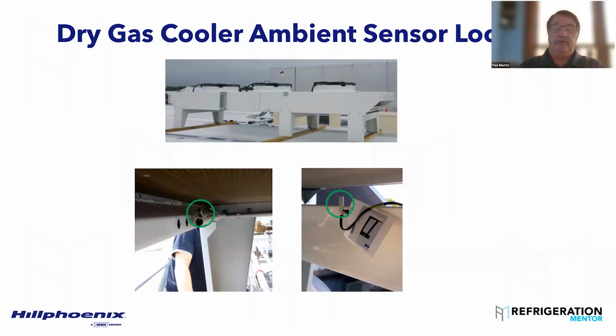So sensor placement is very important. You don't want that ambient sensor out in the sun where at 70 degrees, it might think it's 100 degrees, and that's going to really mess up your condenser control. So we like to get it up underneath, and this is where we mount it today. You'll see we've got it up underneath. We're mounting it in the airstream. It's just like on an adiabatic. I didn't think I would have sent a picture of an adiabatic.